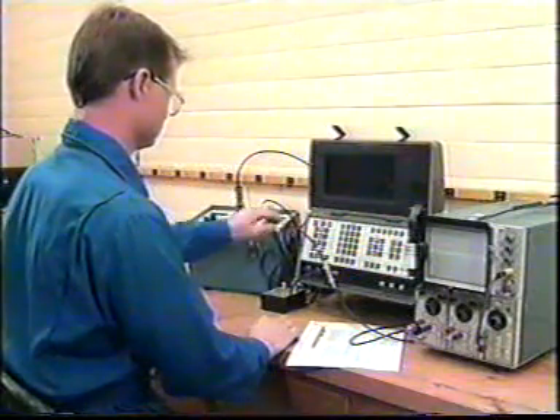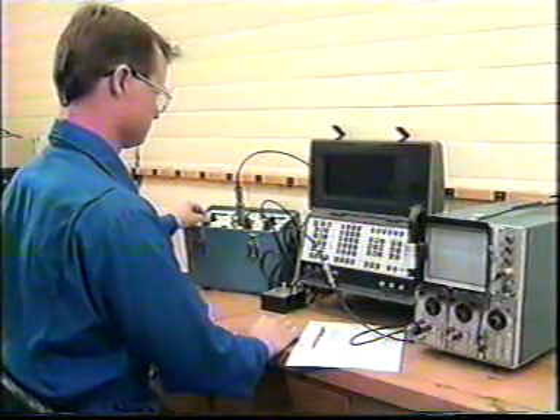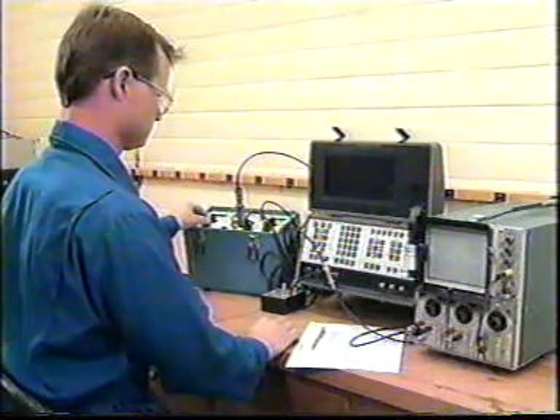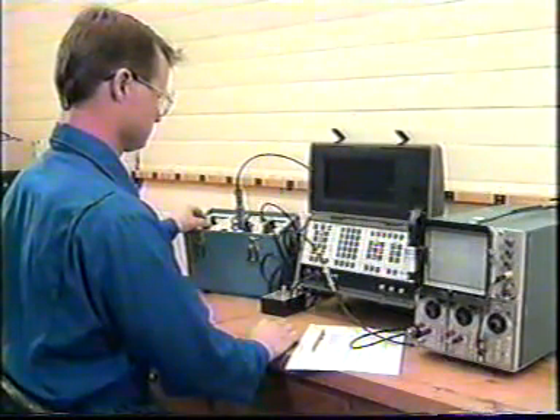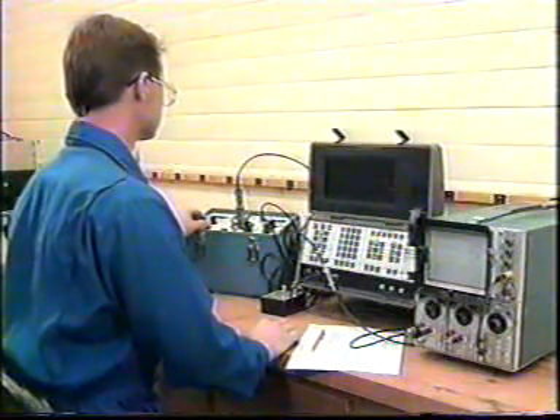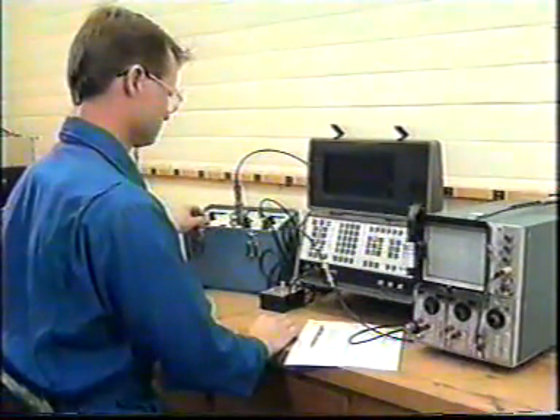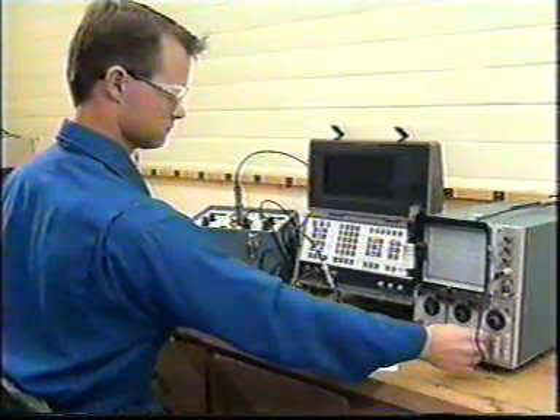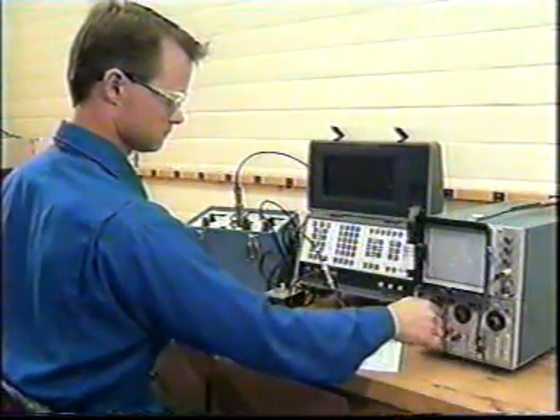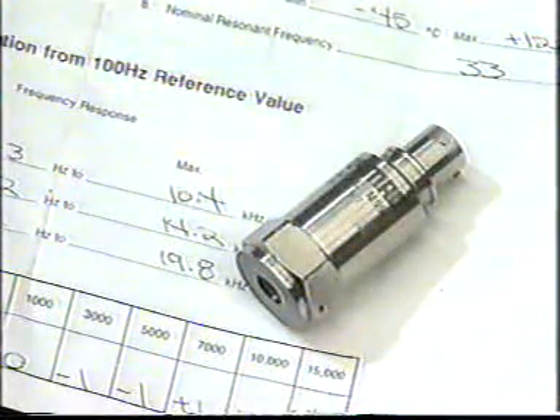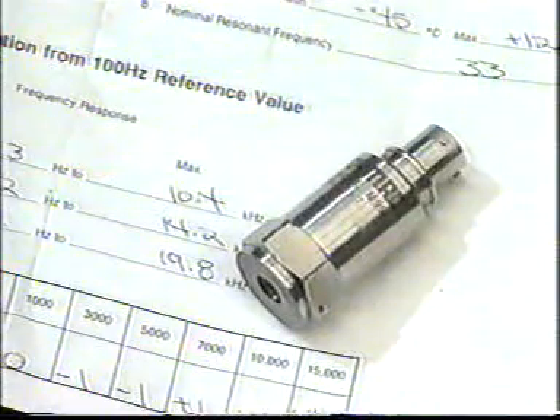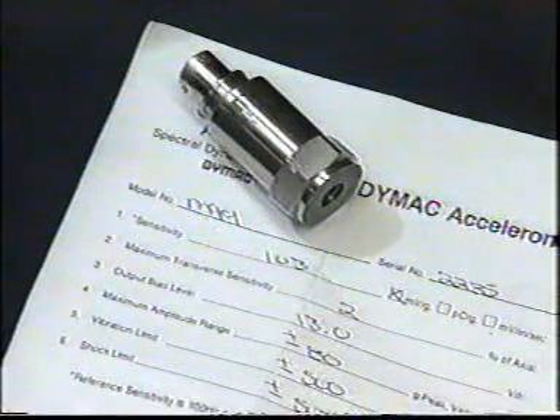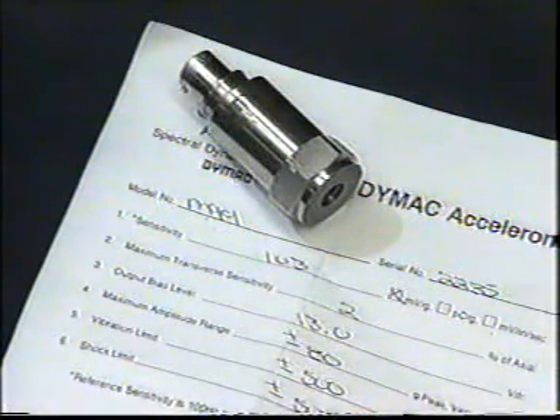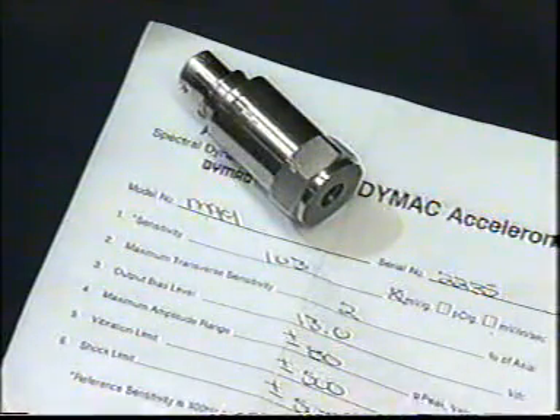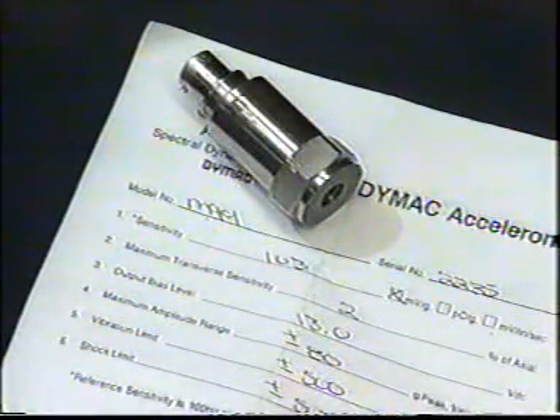Calibration checks the instrument accuracy and repeatability. For vibration, a known motion, such as a shaker table or a special calibration setup, provides the input to the sensor. Measure the output and adjust if necessary. Each manufacturer will have instructions for component or system calibration. Transducer sensitivity can change with time or damage. Each transducer has a calibration constant. This constant is the same as transducer sensitivity. The sensitivity or calibration constant should be checked periodically according to local and manufacturer's requirements.